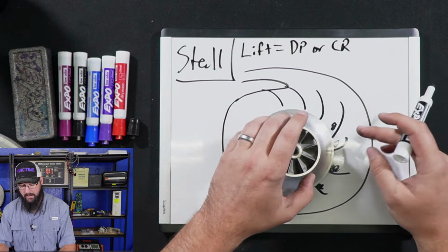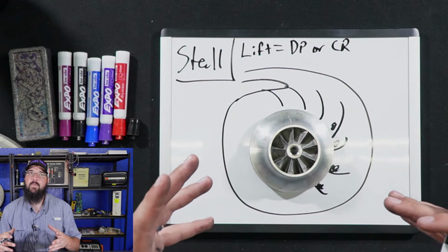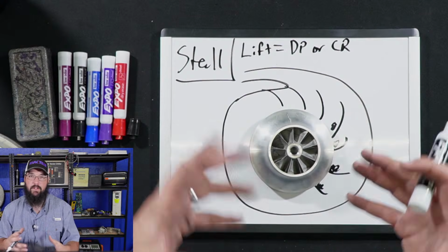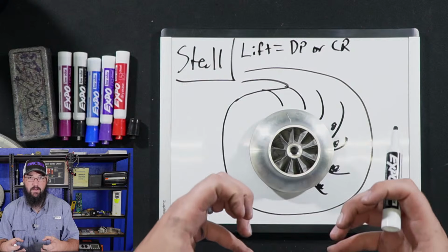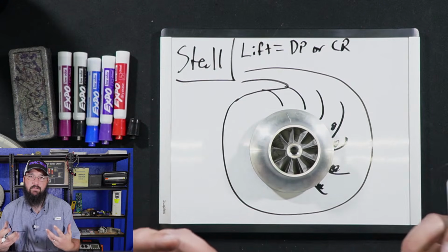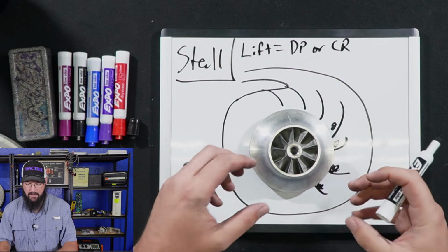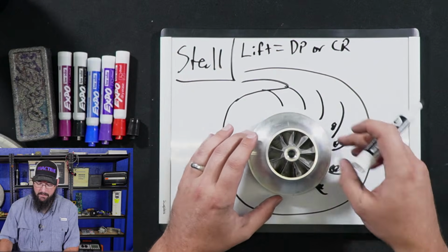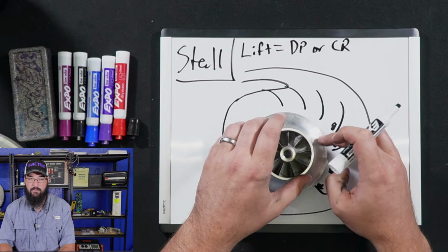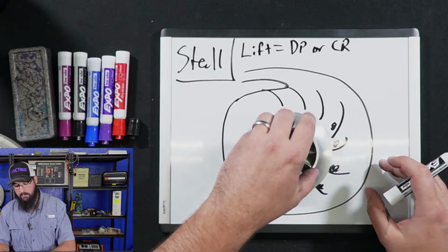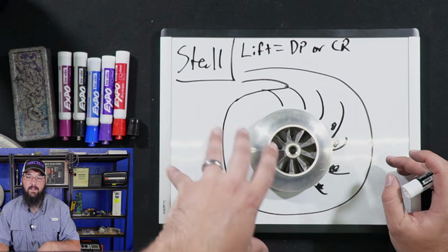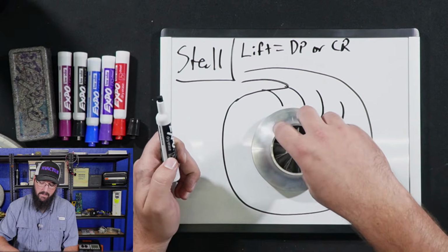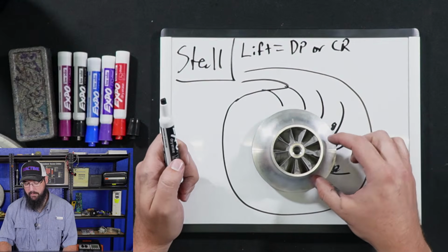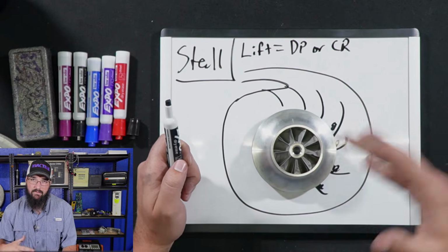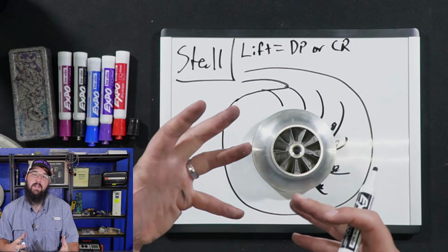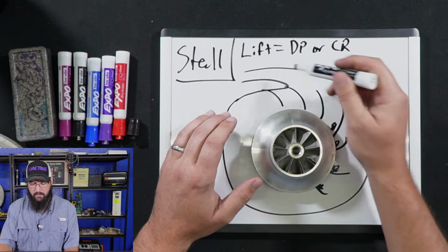So when it gets stuck like that, you'll hear an imbalance happen inside of the compressor. It gets this really grumbly sound, right? I don't know how else to explain it. It just sounds like a low end grumble, like the machine is just sitting there rattling. That's imbalance in the impeller. That imbalance is happening because the refrigerant, as it rotates, is getting stuck. When everything flows properly, the refrigerant is moving in a free state. It's balanced and everything sounds smooth. But as we begin to stall, part of the refrigerant in the impeller as it's rotating is not leaving the impeller, and because it's not able to leave, it becomes an imbalance in the impeller. Anyway, that is what a stall ultimately is.